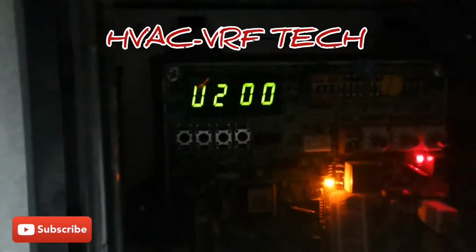Okay guys, so we've got an E439. If we have a look, I already know what the error code is, but just to show you, that is an error due to refrigerant leakage. So we are going to pressurize the system and look for a leak.